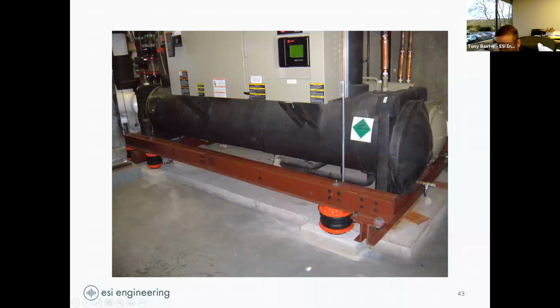How often do those air springs have to be maintained? There are two ways of doing it. You could put leveling valves in, sensing the vertical position of the chiller and adding air as needed, since air is going to leak out. What they do here is come through every week or every month with a pressure gauge on them—you can maybe see one right here—and then use a compressed air source to bring it up to whatever pressure it needs to be at.